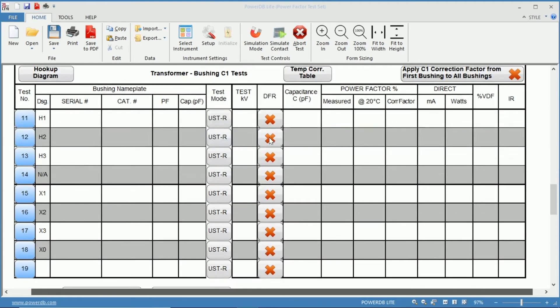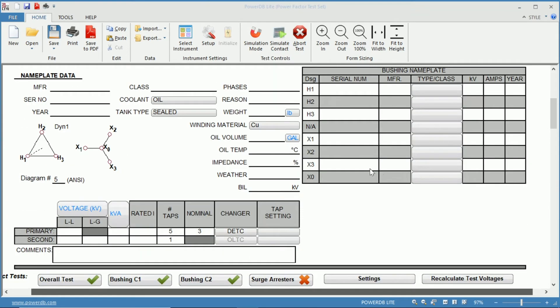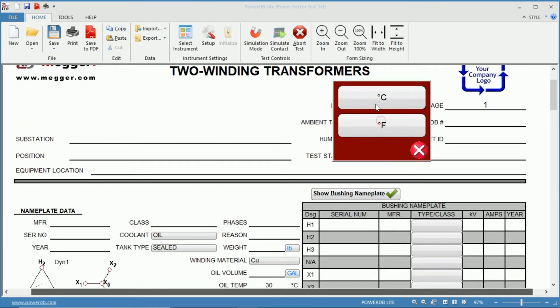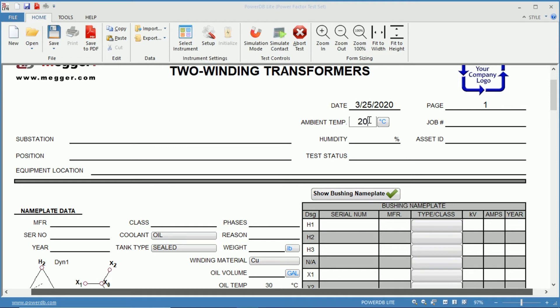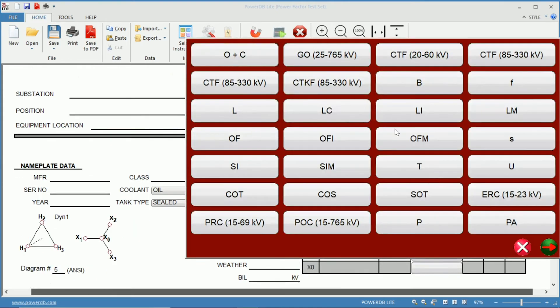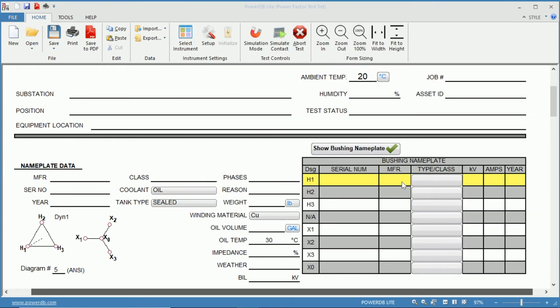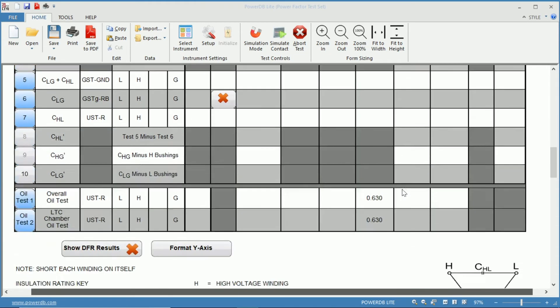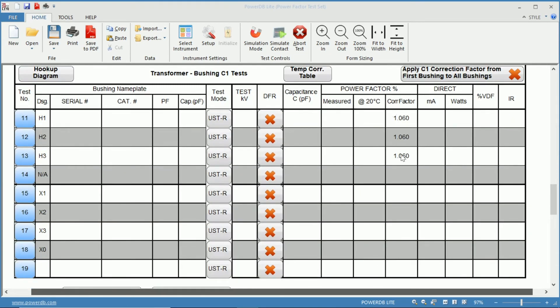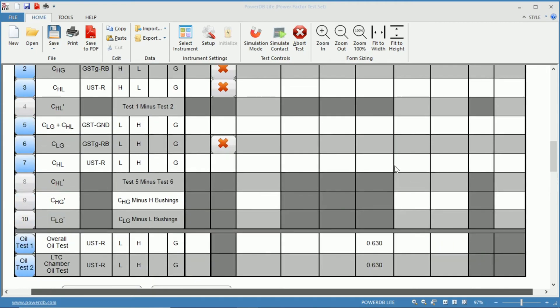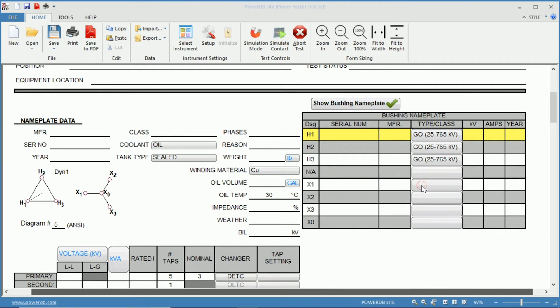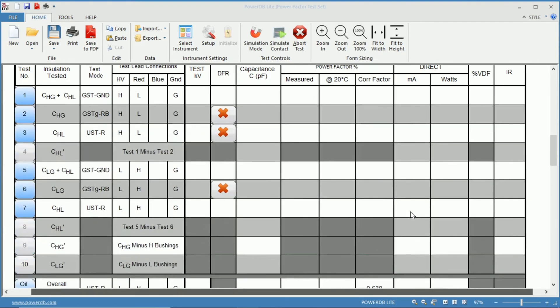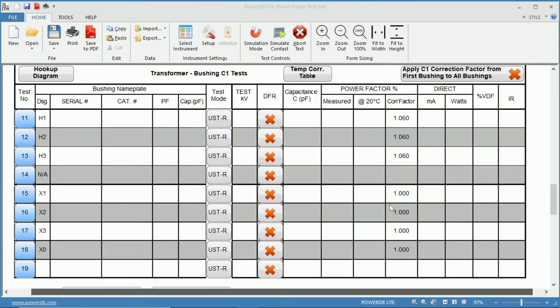It is important to remember that the correction factors do need information, and for the bushings that would be the oil temperature — let's assume 30 degrees C. Ambient temperature, let's assume 20 degrees C. And then the third is the bushing type. If we choose bushing type and scroll down, we can see that we do indeed have a correction factor for our H bushings. And if we were to change our X bushings to a different class and scroll back down, we notice that we have a different correction factor.